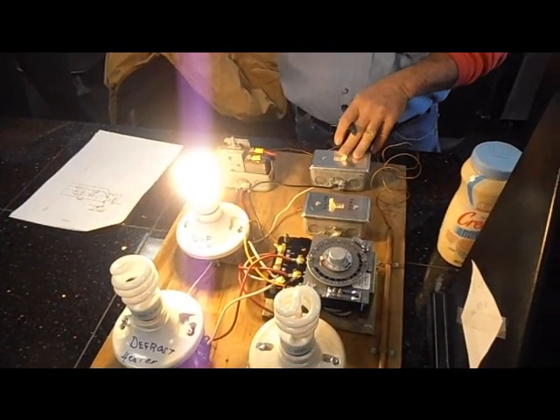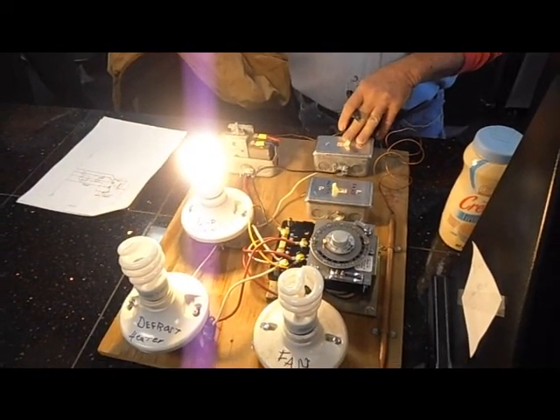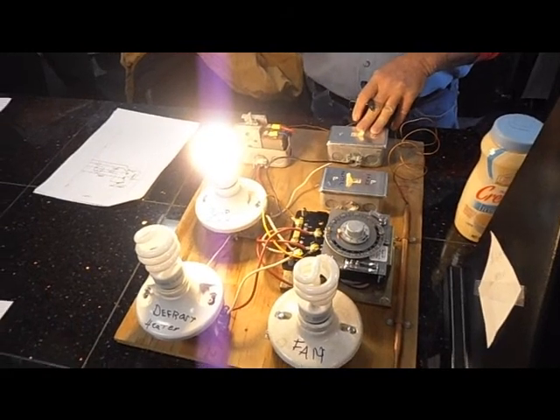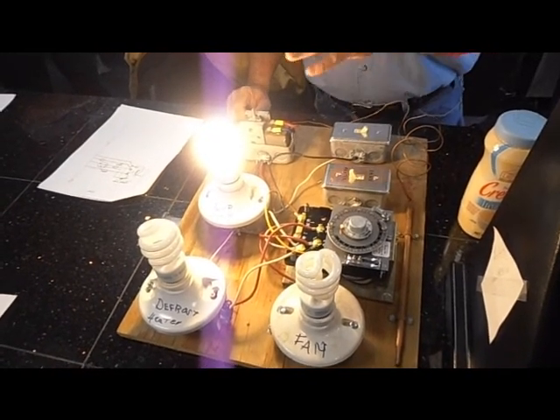Liquid solenoid opens, and then low pressure switch closes, turns the compressor on, and then you start freezing.